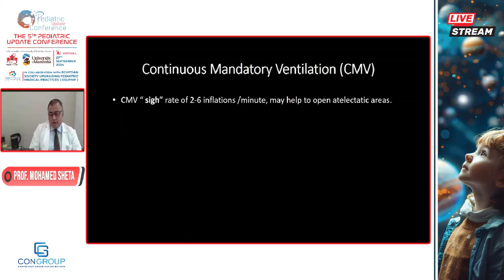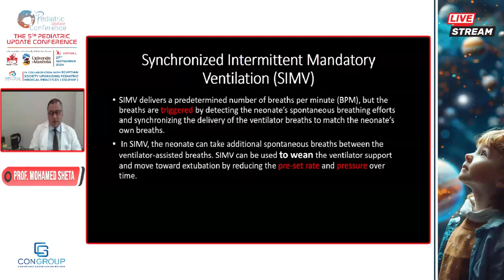Synchronized intermittent mandatory ventilation, or SIMV, is a commonly used mode. It's triggered by detecting the neonate's spontaneous breathing effort through the flow sensor, and then synchronizes the delivery of the ventilator breath to match the neonate's own breath. This decreases conflicts, barotrauma and complications. In SIMV, the neonate can take additional spontaneous breaths between the ventilator-assisted breaths. So SIMV can be used to wean the ventilator support and move toward extubation by reducing the breath rate and pressure. We decrease the rate gradually and decrease the pressure in SIMV mode.